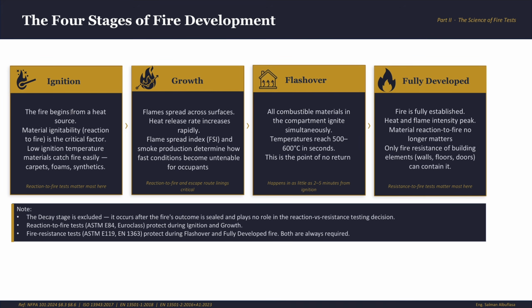After the incipient stage, the fire enters the growth stage. At this stage, it finds more fuel and oxygen to consume or burn. During this stage, the fire becomes larger and more intense. The heat release rate increases as the fire spreads. If conditions continue to worsen, the growth stage might eventually lead to flashover. It's when all combustible materials in the compartment ignite simultaneously.